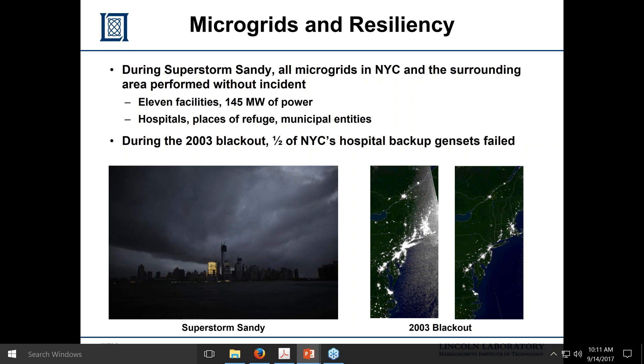What ended up happening in the 2003 blackout was that half of New York City's hospital backup generators failed. We see that in DOD installations as well — backup generators that don't work because they haven't been tested in two years, they have no fuel, or mice chew the wires. In a microgrid, systems are always on and always engaged — you're always making sure they're operational. It's a different mindset than having just a backup generator.